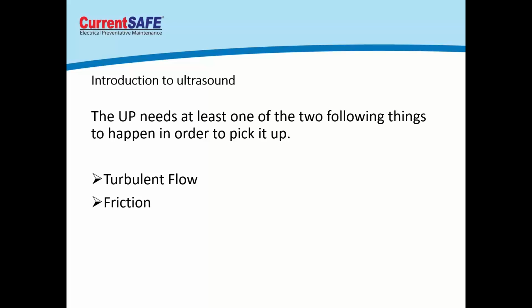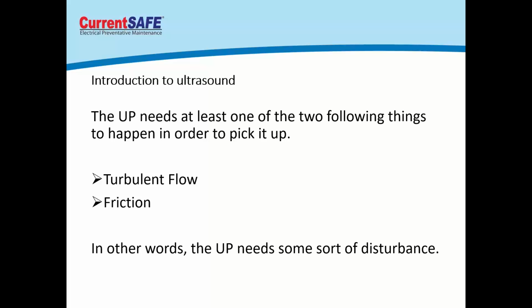This is why it's so good at early detection: those things happen at a very high frequency, in the 20 to 100 kilohertz range, which the ultra probe picks up. Then through a process called heterodyning, it changes that signal from something we can't hear into something we can hear, converting it into a signal we can analyze with their software to figure out what it is.